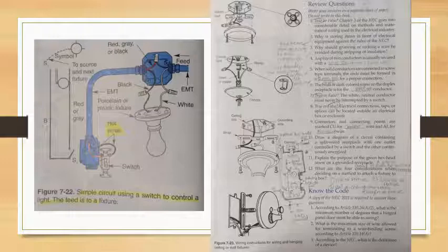Question 7. True or false. The white neutral conductor must never be interrupted by a switch. And that is a true statement. Question 8. True or false. Electrical connections, taps, or splices can be located outside of an electrical box or enclosure. That is false. They must always be protected and kept away from the reach or easy access, for safety reasons, obvious safety reasons. Question 9. Connectors and connecting points are marked CU which means blank wire and AL which means blank wire. Fill in the blank. First blank would be copper for CU and aluminum for AL.